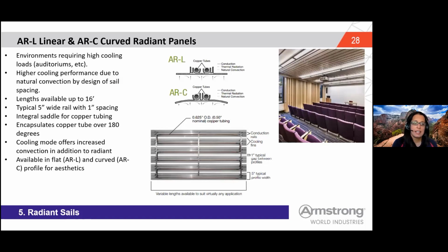And then we have our radiant sails. This is either the ARL, which is linear, or the ARC, which is the same thing but curved. This would be used in environments with a high cooling load, such as high occupancy areas like auditoriums. They have higher cooling performance due to natural convection. As you can see, there are a couple rails with 1-inch spacing in between, so they utilize that natural convection. These are also great if you need a solution with very minimal space.